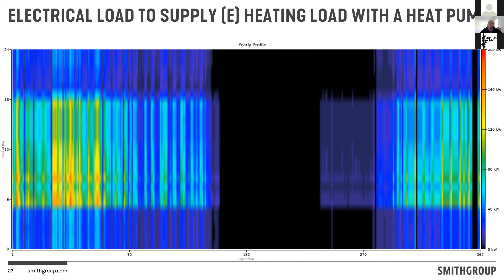You can also quickly see some of the peaks on the lower left, these red spots. These are the cold time of year, morning warm up, and that represents their peak load. A lot of folks, when looking at buildings, design around peaks. When doing that with air source heat pumps, you need to be careful, because you will radically oversize a system if you design around that hour. I don't need that much power, that much heat, for that long—I just need it for a brief window.